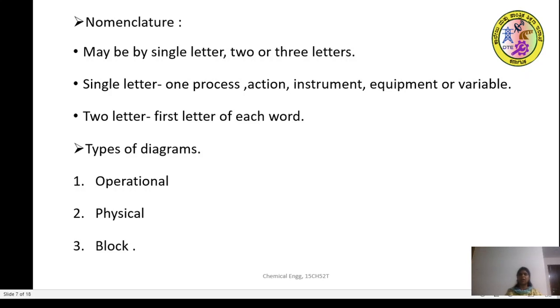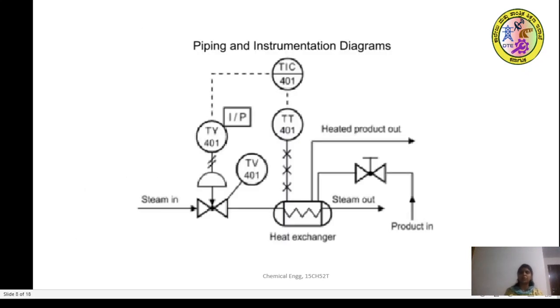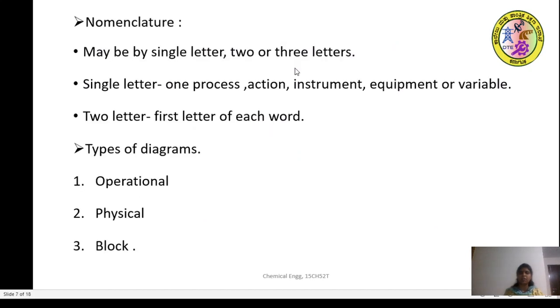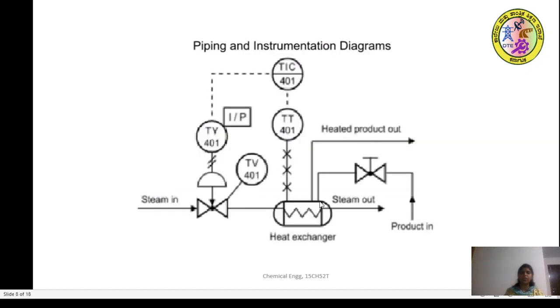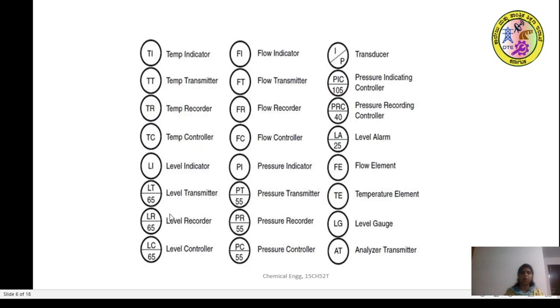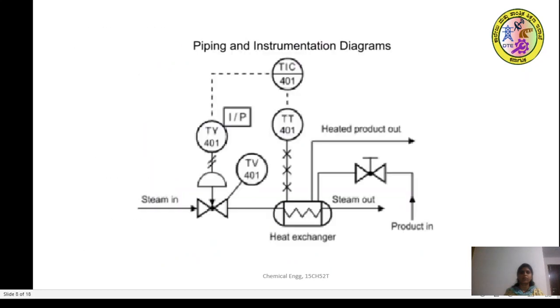in an instrumentation diagram. What are the types of diagrams? You have an operational diagram, a physical diagram, and a block diagram. This is an example of a typical instrumentation diagram. You can see I/P is the transducer, TIC is the temperature indicator controller, TT is the temperature transmitter, the heat exchanger is represented like this, with the steam in valve. TV is what? It is a valve representation. Steam out, this is where the heated product goes out like this.